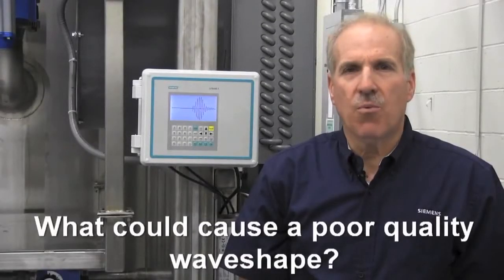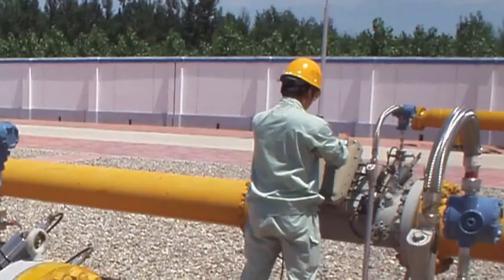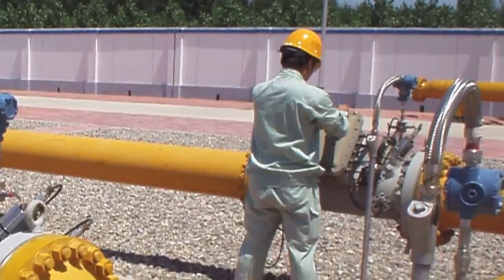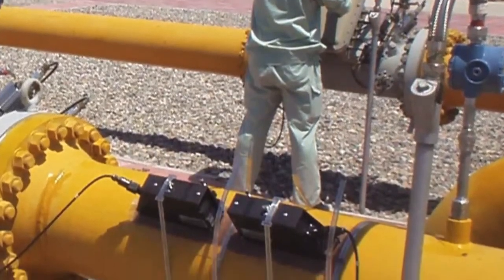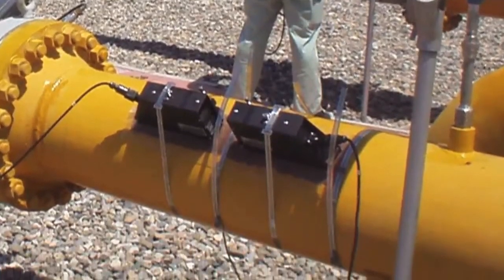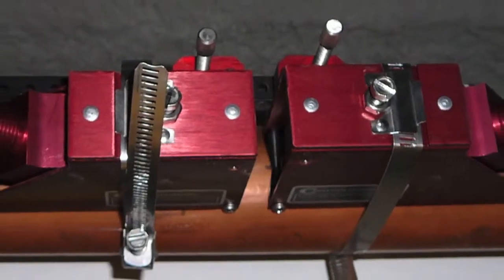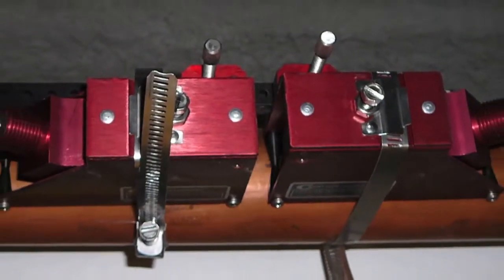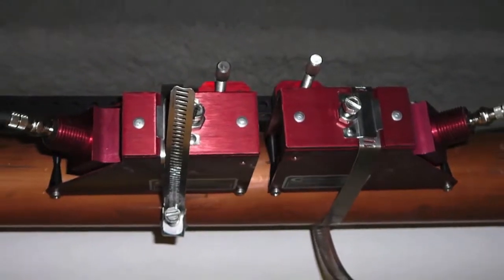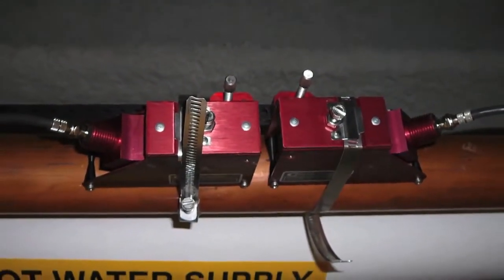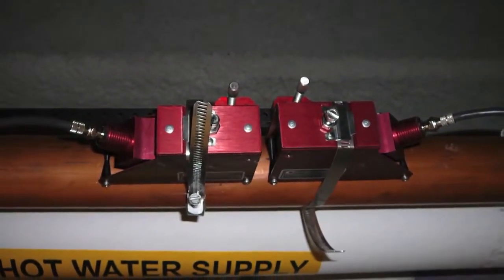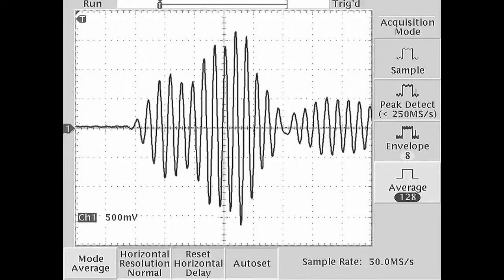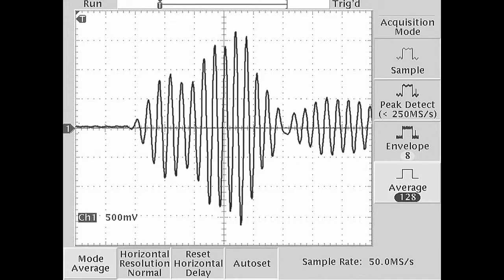What could cause a poor quality wave shape? Siemens sensors are selected by the pipe they are to be installed on. This ensures optimal matching between the sensors and pipe, producing a well-defined, stable waveform. Therefore, only a mismatch can result in a low-quality signal shape. Such a mismatch can occur if an incorrect sensor is selected, or the pipe is of a different dimension than originally specified.